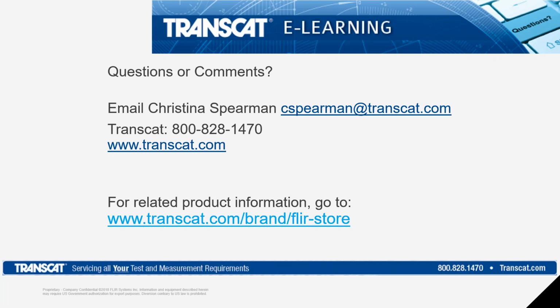All right, another one, a follow-up to the calibration. How much does it cost to calibrate? It depends on the camera model, but I'd be guessing a little bit, around $500, maybe up to $1,000 on one of our very high-end cameras. Another follow-up is, who does the calibration? Does FLIR do it? Yes, FLIR does it. You could send it directly to FLIR, or if you bought it through Transcat, you could send it to Transcat, and then they would send it to us as well. We have a specified lab at our office in Nashua, New Hampshire, that goes through a 20 or 30 point test that we use to calibrate these.